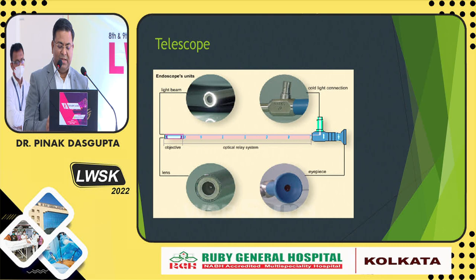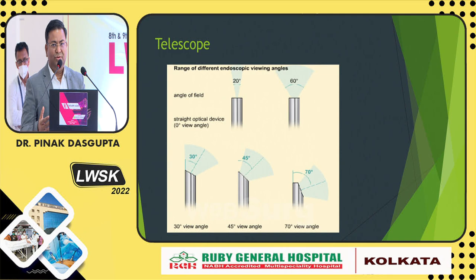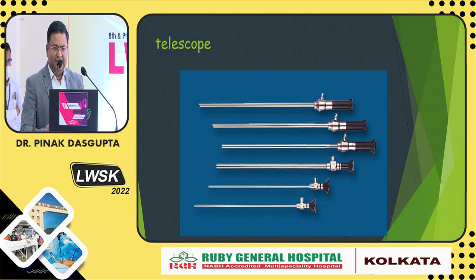Telescopes come in 0 degree or 30 degree, which is most commonly used; 45 degree and 70 degree are also available to increase the field of view. They range from 3 millimeter diameter up to 12 millimeter, and from 33 centimeters long up to 45 centimeter bariatric scopes.